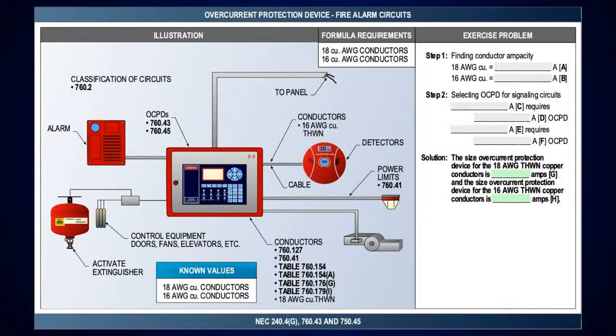And then we did a setup here. This is actually a pretty cool illustration because they actually drew the new equipment and everything, and what you would see, the activated extinguishers, the alarm, the detectors and everything like you would see out in the field. And we're going to have you do here a number 18, number 16. You're going to do the exact same thing. You're going to go look at table 310.16 and get the amperage there, not size it, and then size your overcurrent protection device for those signaling circuits.